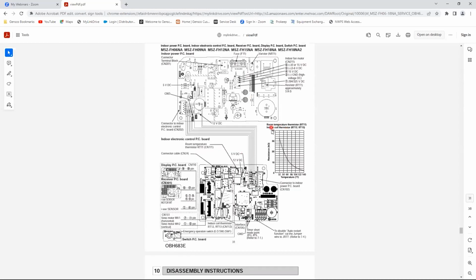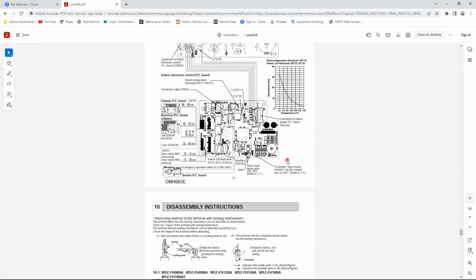So we come down here. We talked about thermistors a few seconds ago, your room temperature thermistor and your indoor coil thermistor. Here is your value curve chart. On the left side, you'll see your resistance in K ohms, and on the bottom, you will see your temperature in Fahrenheit. So if your room temperature is 68 degrees, we follow that up and you're going to be about 12 to 13 K ohms on your thermistor. That would indicate that they are good.